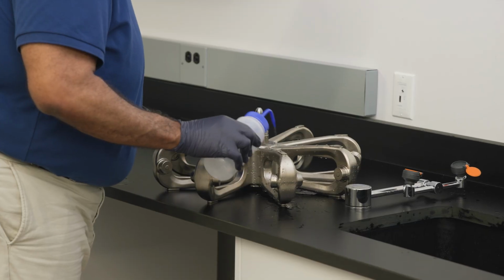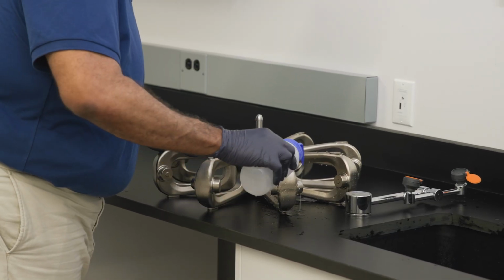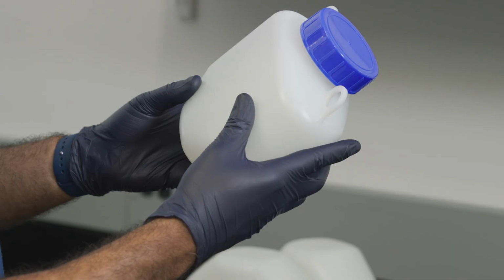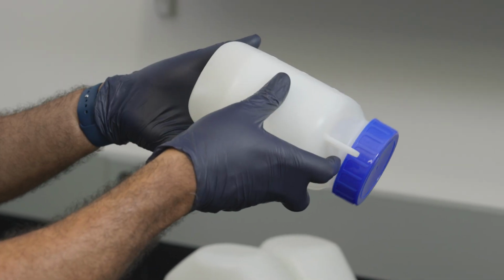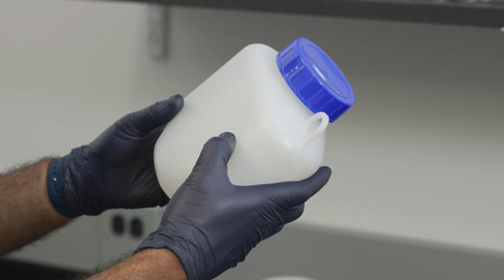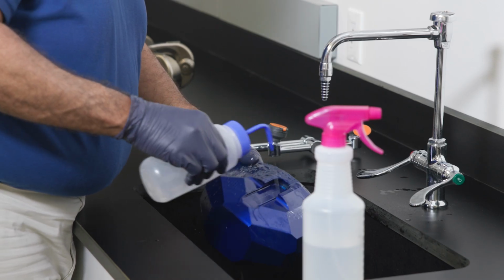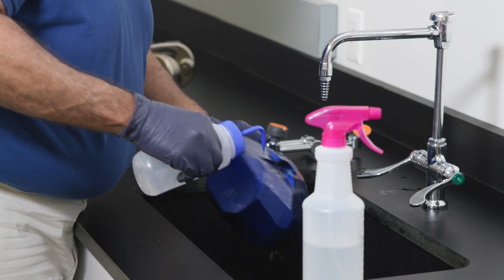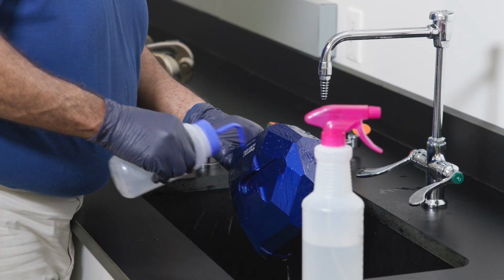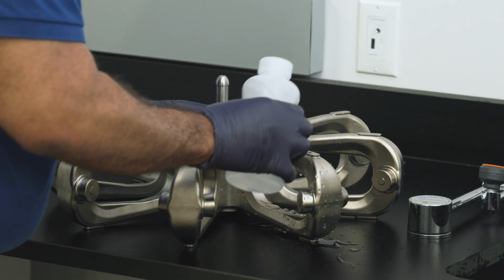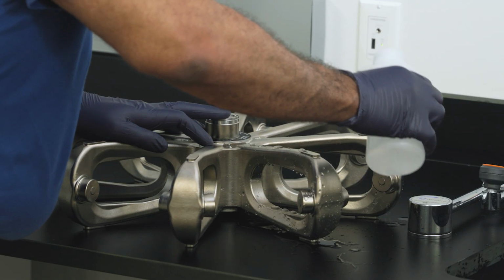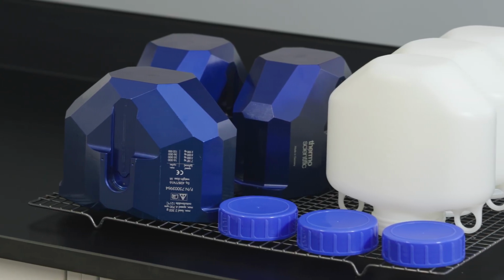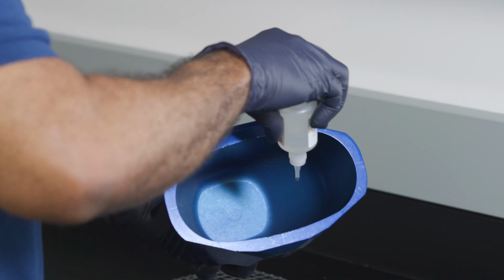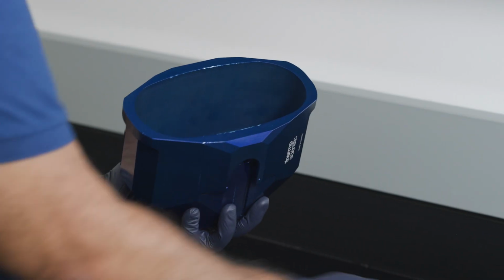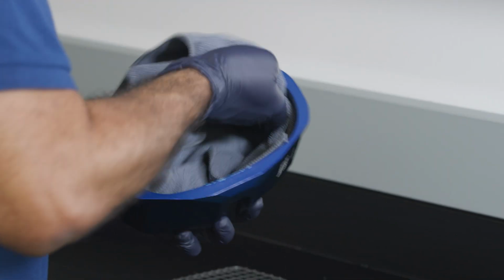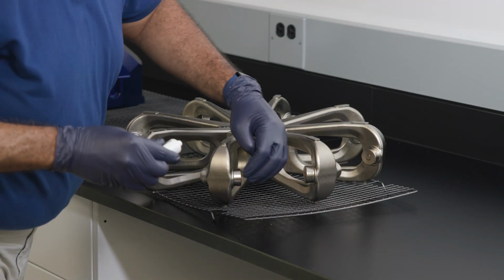In case of contamination, disinfect and decontaminate the affected parts immediately. Equipment can be damaged by inappropriate disinfection methods or agents. Again, check that the disinfection agent or method used won't damage the equipment. After disinfecting all components, rinse the centrifuge and accessories with water and allow them to fully drain and dry. Once again, treat aluminum parts and their cavities with corrosion protection oil, and treat the bolts of the swing-out rotor with bolt grease.